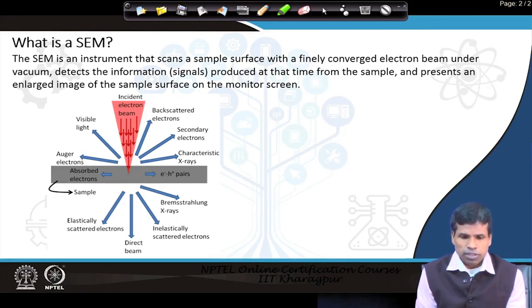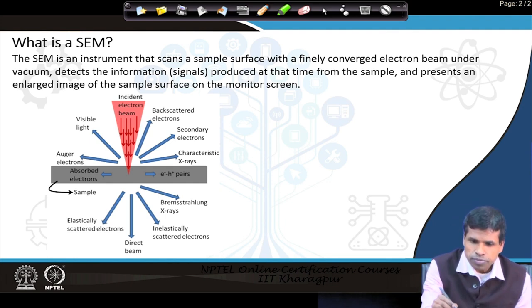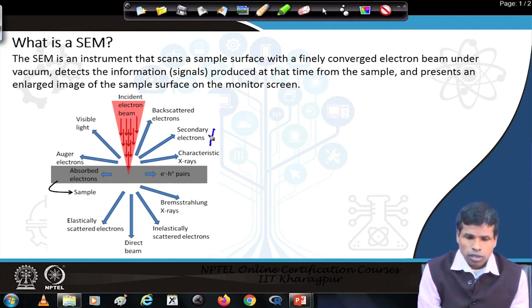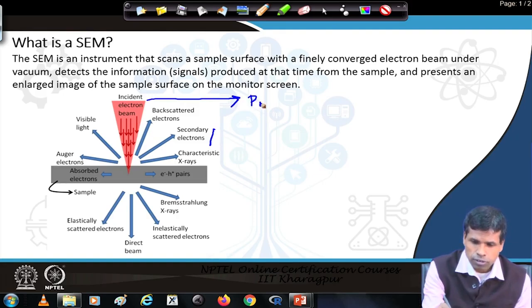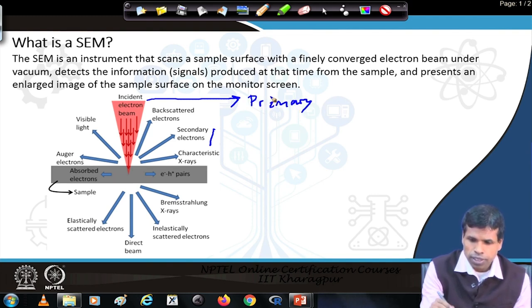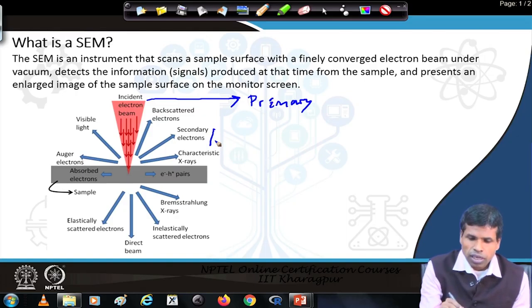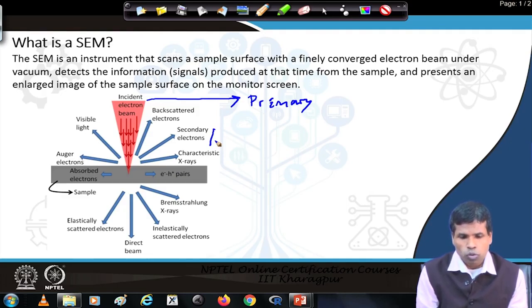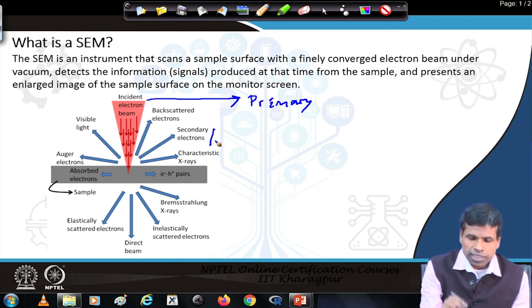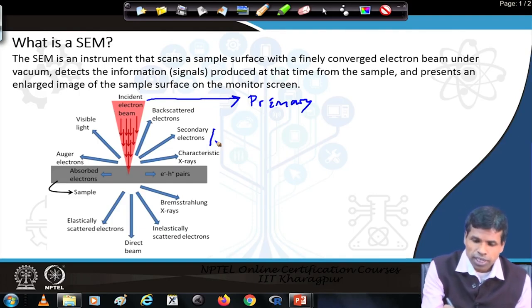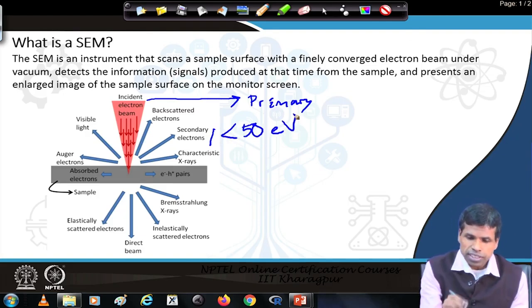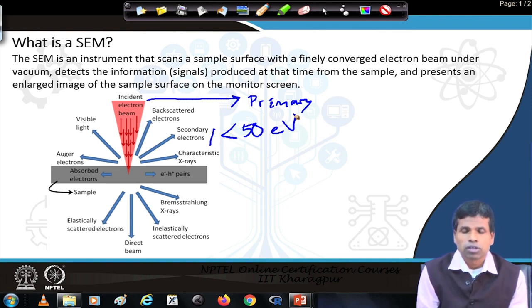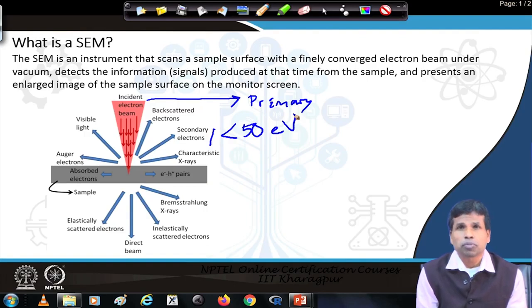The major type of signals that come out from the sample include secondary electrons. We call them secondary electrons because the electrons incident on the sample are the primary electrons. Primary electrons have energy normally from 100 volts to around 30 kilovolts, and secondary electrons have much less energy — normally less than 50 eV. These secondary electrons are primarily used for scanning electron microscopy, providing us the three-dimensional morphology of the specimen.